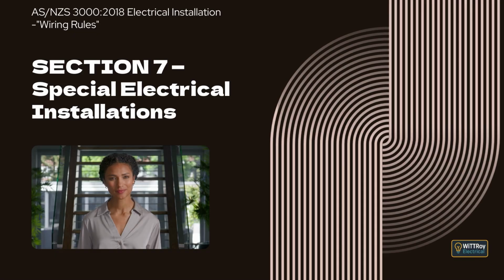Clause 7.2.1.1 Scope. This clause explains that the requirements of Clause 7.2 apply to building services that are essential for safety. These include systems needed for fire detection, warning and extinguishing, smoke control, evacuation systems, and any electrical systems that protect the safety of people who rely on lifts during emergencies. The key idea is that these systems must remain reliable so they can function when they are most needed.